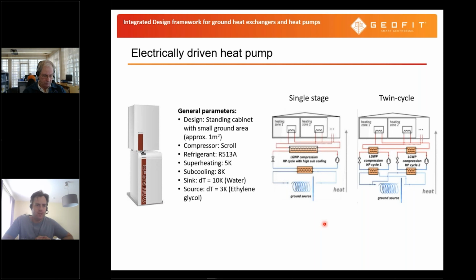This is with the manufacturer Ochsner. So it's a heat pump with a standing cabinet. The compressor technology is a scroll compressor. The refrigerant is more or less a trade-off. We aimed for a really low GWP refrigerant, but at that moment it was not allowed by the manufacturer, so we had to deal with R513A. That is not a completely low GWP approach, but it is a medium GWP approach. Further, the superheating, subcooling, and certain parameters, so this is our approach for the electrical driven heat pump in GEOFIT.